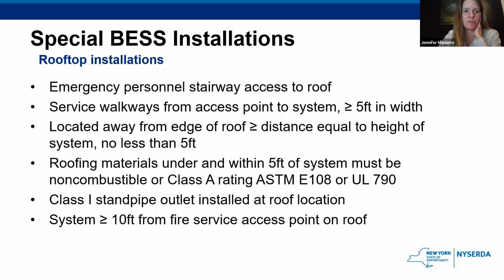Okay, so special requirements for rooftop installations. Emergency personnel need to have stairway access to the roof. Once they get up there, they need access to the system, a pathway that's at least 5 feet in width. The system needs to be located away from the edge of the roof at a distance of no less than 5 feet or the height of the system. Obviously, you want the roofing materials under and around the system to be non-combustible. There should be a Class 1 standpipe outlet installed at the roof location so you can have water if you need it. And the system should be at least 10 feet from the fire service access point on the roof. You wouldn't want emergency personnel going up that stairway in the first bullet just to be head on with the energy storage system as soon as they open the door, right? So at least 10 feet away from that access point.